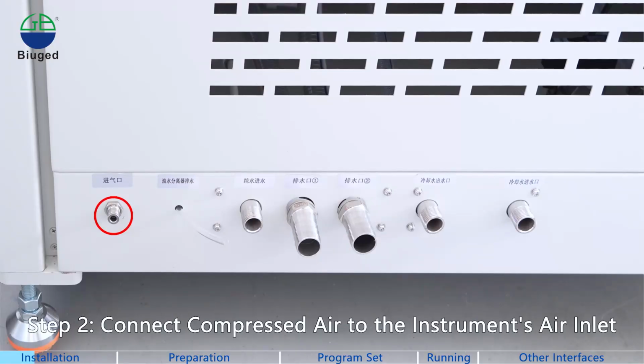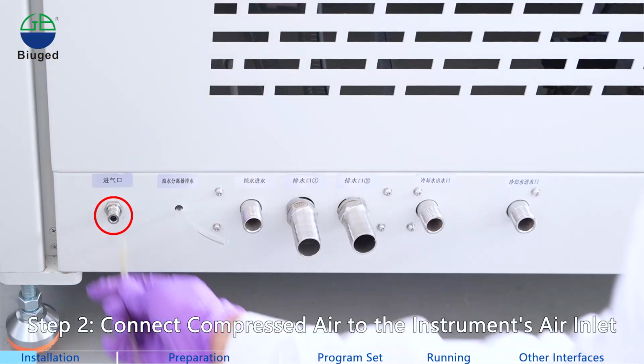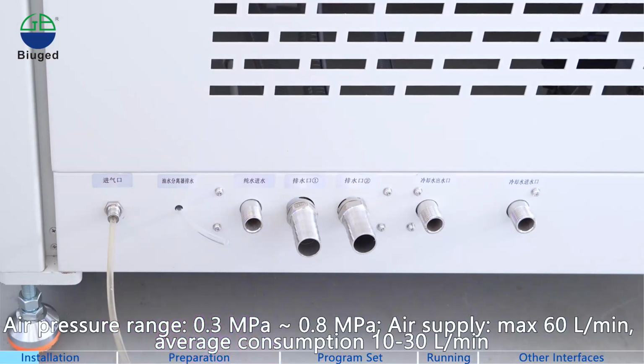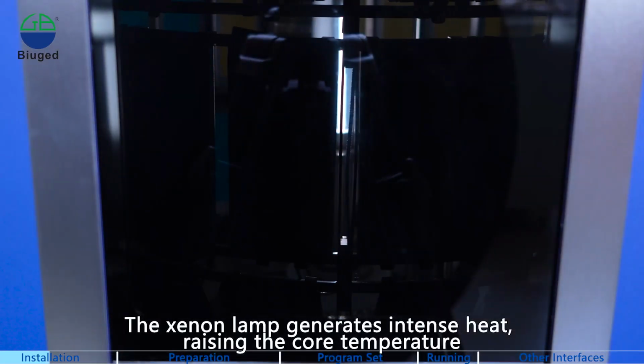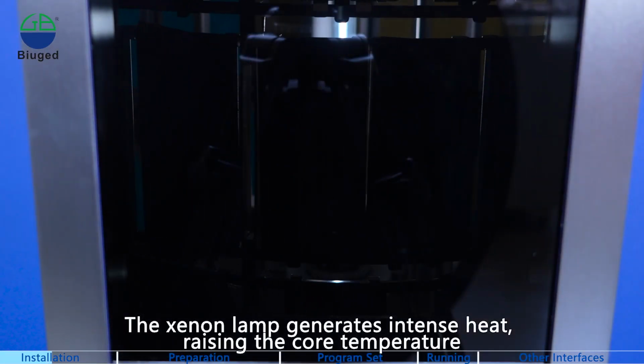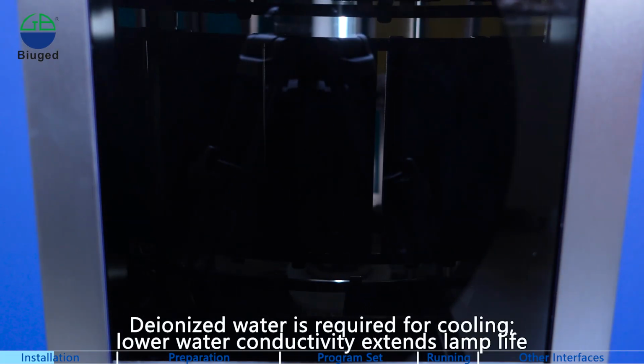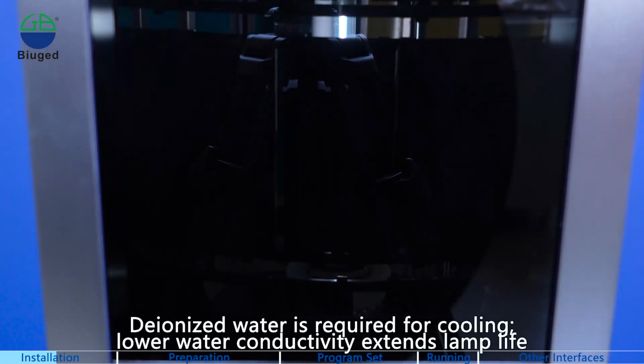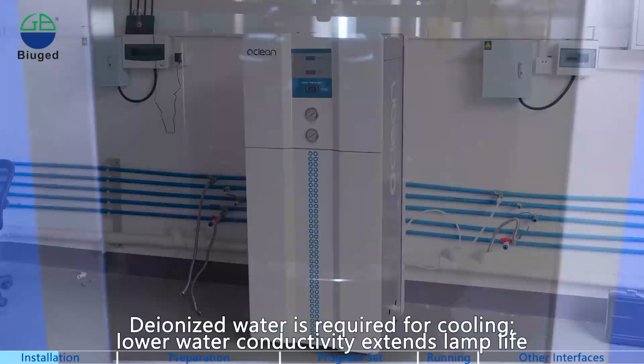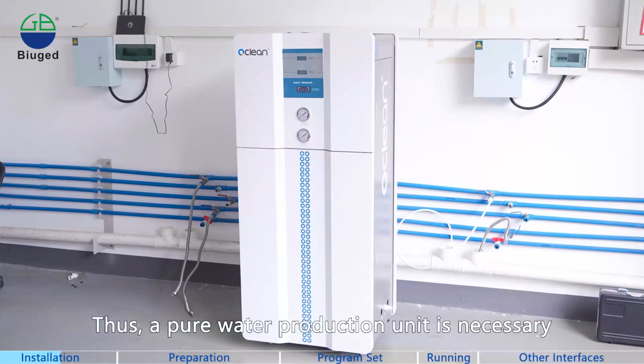Step 2. Connect compressed air to the instrument's air inlet. Air pressure range, 0.3 MPa to 0.8 MPa. Air supply, max 60 liters per minute, average consumption 10 to 30 liters per minute. The Xenon lamp generates intense heat, raising the core temperature. Deionized water is required for cooling. Lower water conductivity extends lamp life. Thus, a pure water production unit is necessary.